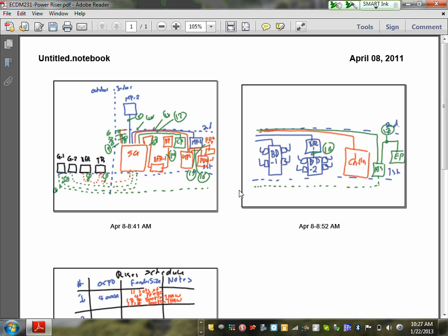And at that point, we're chugging along off the utility. The utility breaker is closed. All the generator breakers are open. Okay. Utility leaves. We have sensors, like voltage sensing relays, whose job is to verify what the voltage on the line side of that breaker is. If it starts dropping over a certain amount of time, that will automatically send a start signal to the generator and trip the utility breaker open.